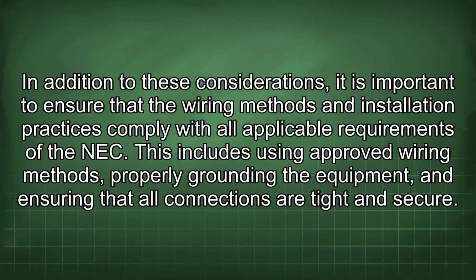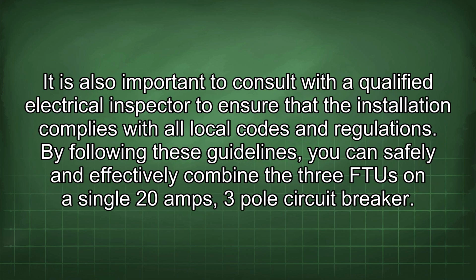In addition to these considerations, it is important to ensure that the wiring methods and installation practices comply with all applicable requirements of the NEC. This includes using approved wiring methods, properly grounding the equipment, and ensuring that all connections are tight and secure. It is also important to consult with a qualified electrical inspector to ensure that the installation complies with all local codes and regulations. By following these guidelines, you can safely and effectively combine the 3 FTU on a single 20 amp 3-pole circuit breaker.